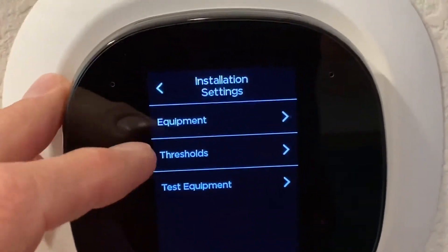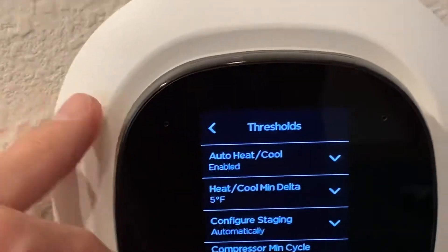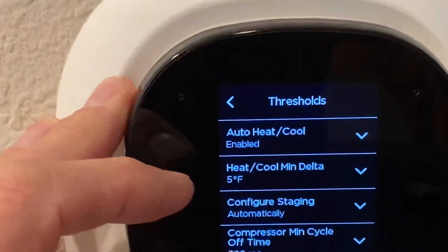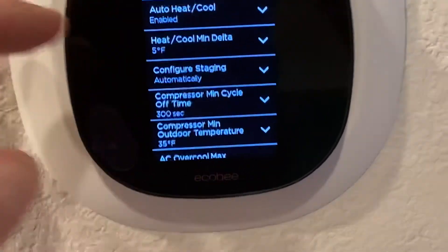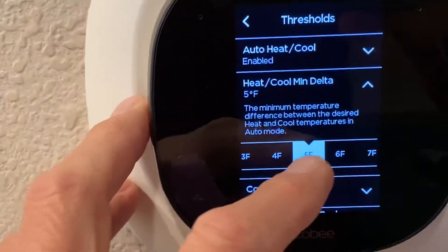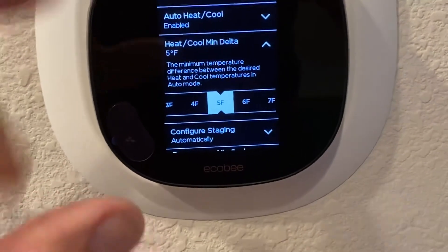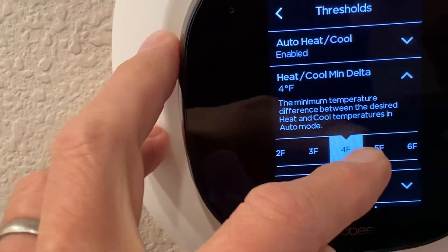This section is actually pretty useful: Thresholds. You'll see Auto Heat/Cool Enabled, and then Heat/Cool Minimum Delta — that's basically the difference between your two temperatures, your low temperature and your high temperature. You can go in here and change that to 3 degrees, 4 degrees, whatever. You can keep it really tight like 71 and 69 degrees, or make it wider. It looks like 3 degrees Fahrenheit is the lowest, but let's go to 4.